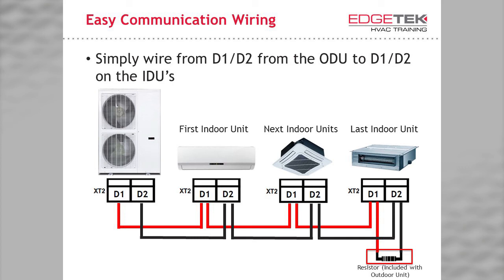To wire the units up, you'll be wiring in a daisy chain starting with the outdoor unit terminals D1 and D2. From there, we go to our first indoor unit, then to all of our other indoor units, and then to our last indoor unit, in a chain. There, we will be installing a resistor across D1 and D2 at the last unit's terminal block. This is included with each outdoor unit.